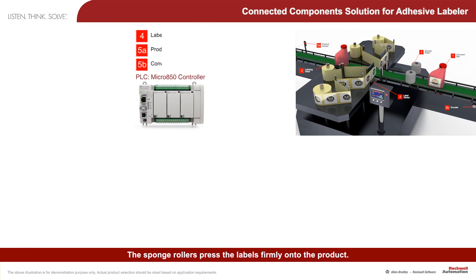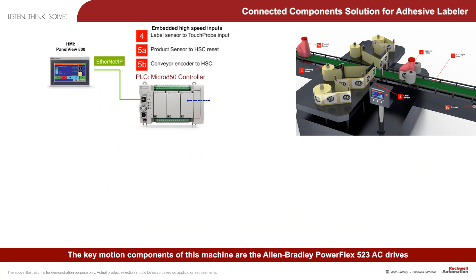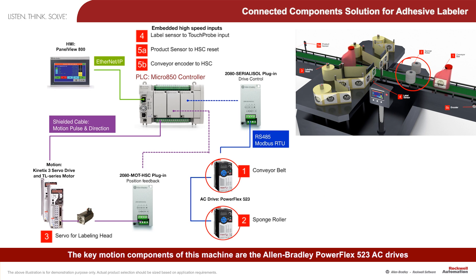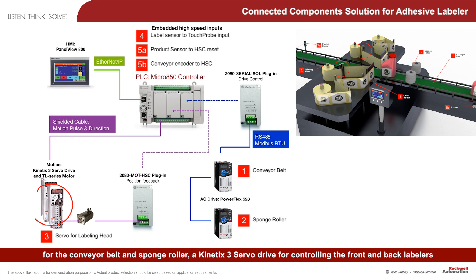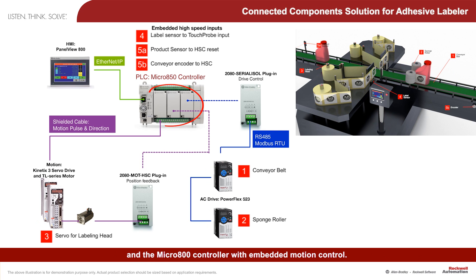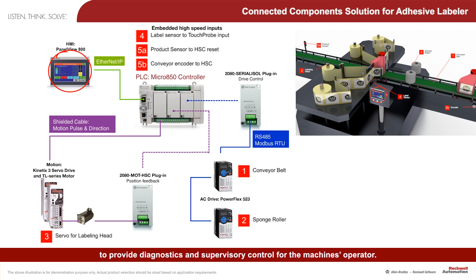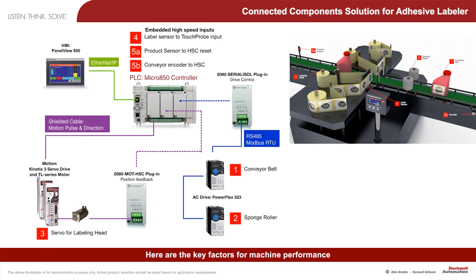The sponge rollers press the labels firmly onto the product. The key motion components of this machine are the Allen-Bradley PowerFlex 523 AC drives for the conveyor belt and sponge roller, a Kinetix 3 servo drive for controlling the front and back labelers, and the Micro 800 controller with embedded motion control. The HMI PanelView 800 is connected to the Micro 800 controller over EtherNet/IP to provide diagnostics and supervisory control for the machine's operator.